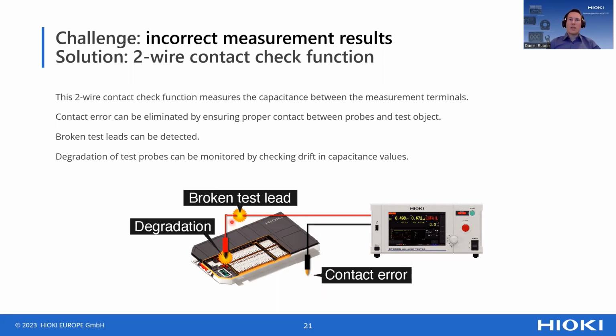So you might need to do the testing again because the points were not probed correctly, or it can be a hint that the test leads are broken or that your tips are being worn off. Even looking at the capacitance values, if you see a drift over time, it will give you an idea that, for instance, the tips are wearing off slowly, and therefore replacement of the tips is recommended in the near future.